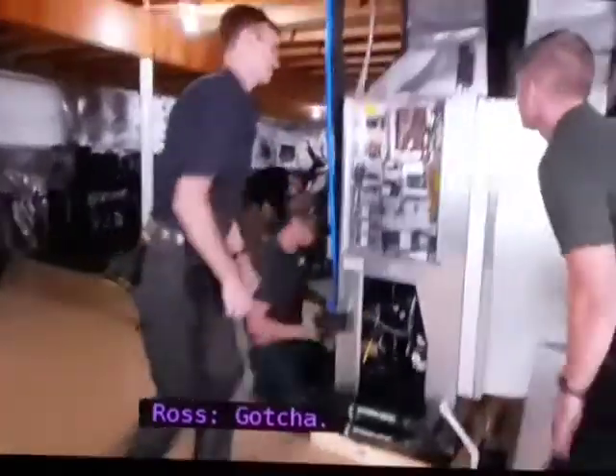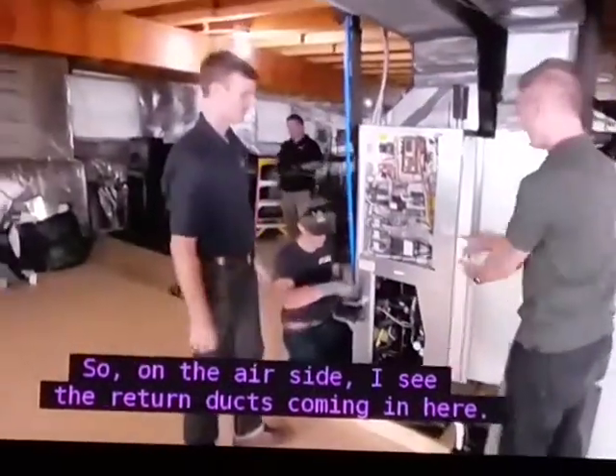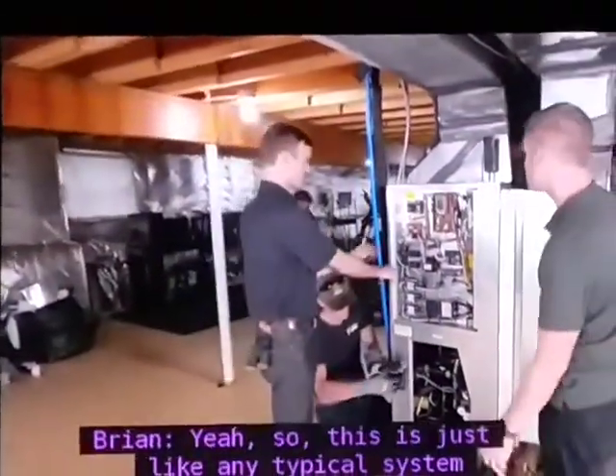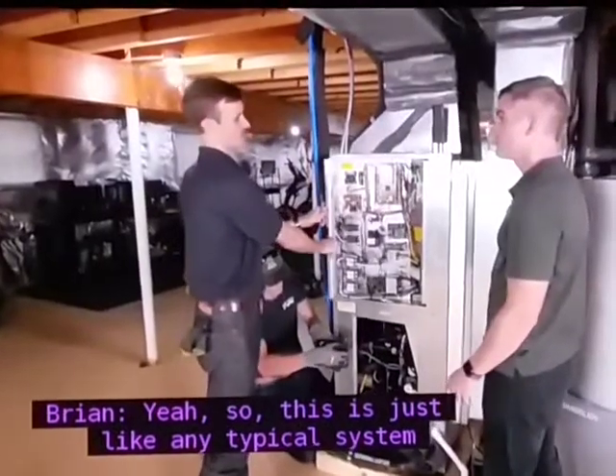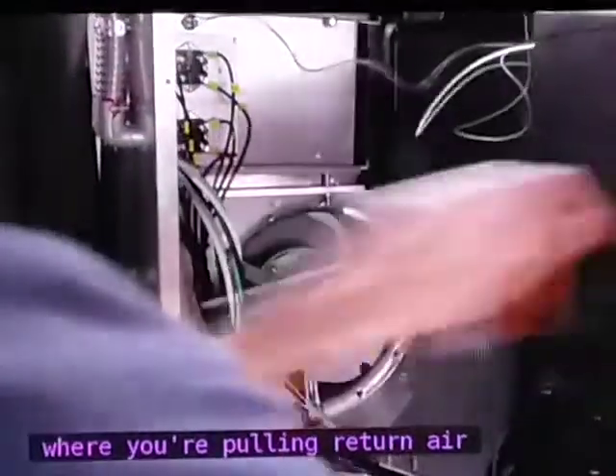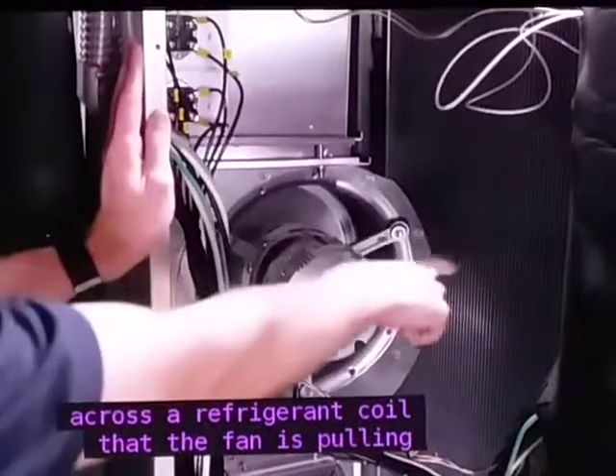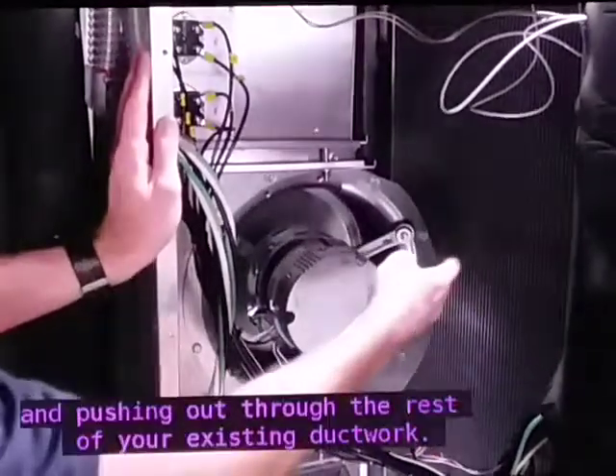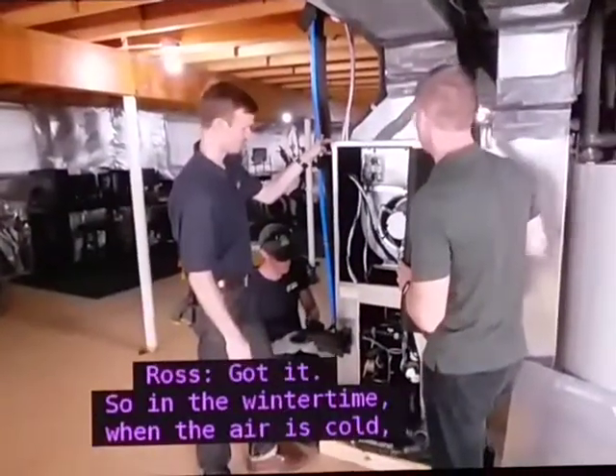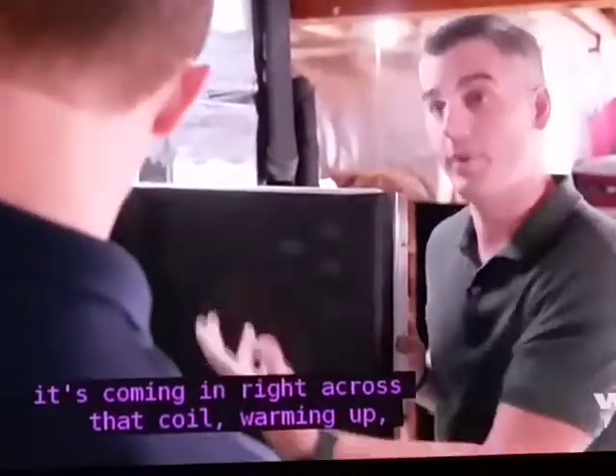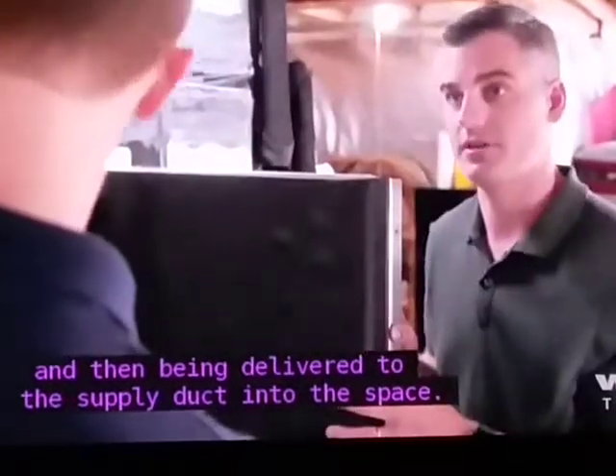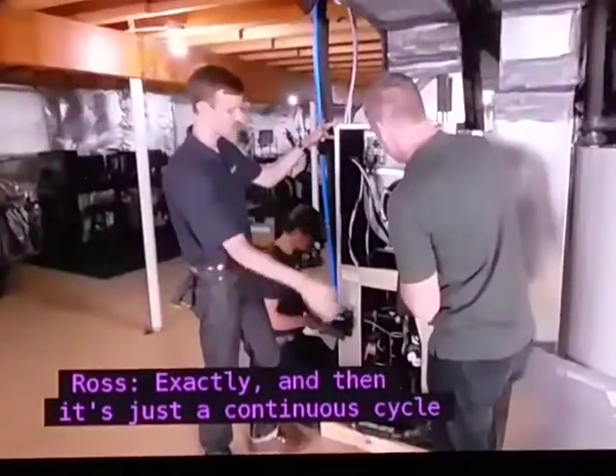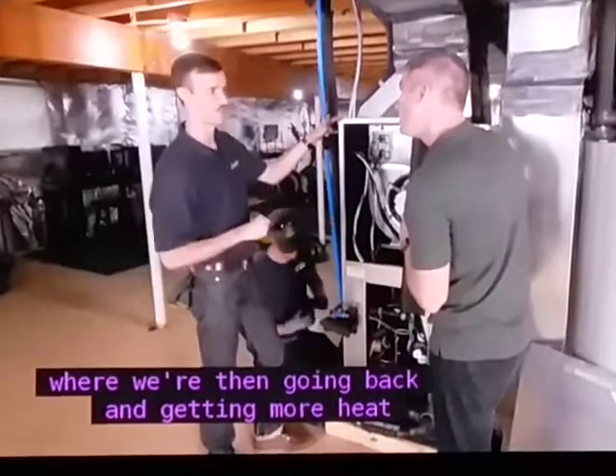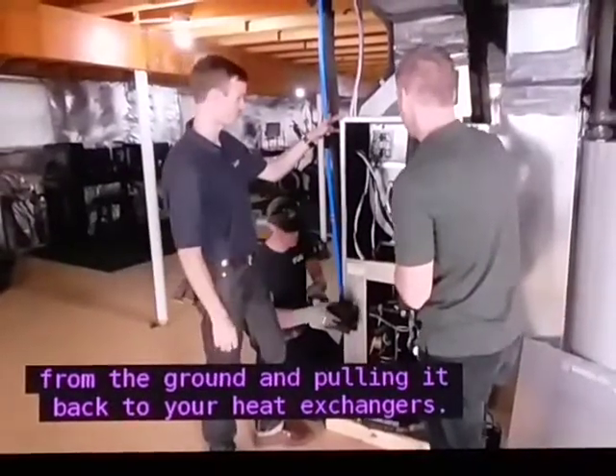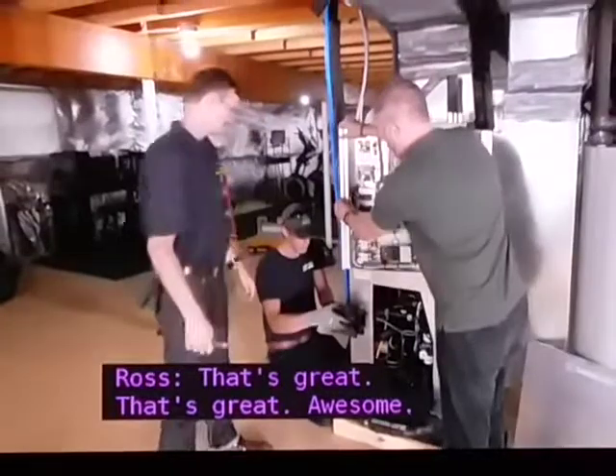Gotcha. So on the air side, I see the return ducts coming in here. Exactly. Yeah, so this is just like any typical system where you're pulling return air across a refrigerant coil that the fan is pulling and pushing out through the rest of your existing ductwork. Got it. So in the wintertime, when the air is cold, it's coming in right across that coil, warming up, and then being delivered to the supply duct into the space. Exactly. And then it's just a continuous cycle where we're going back and getting more heat from the ground and pulling it back to your heat exchangers. That's great. Awesome.